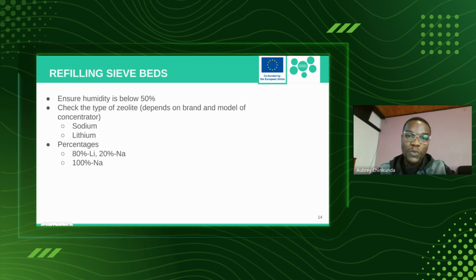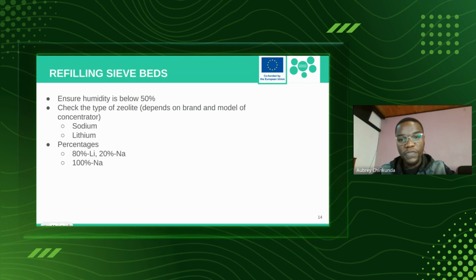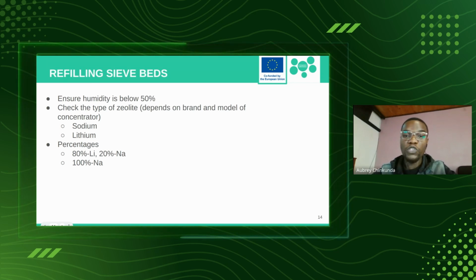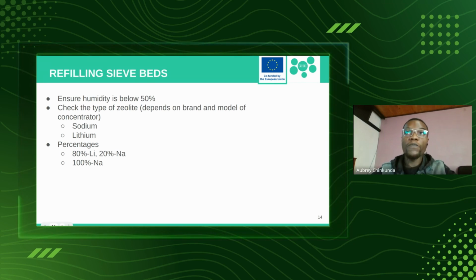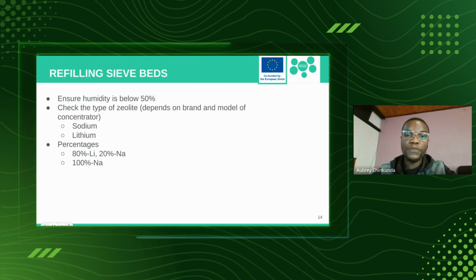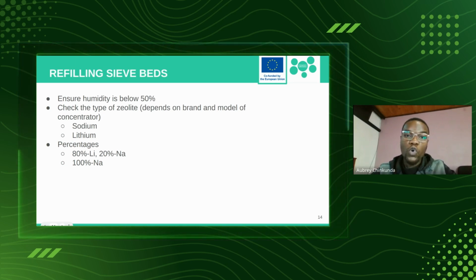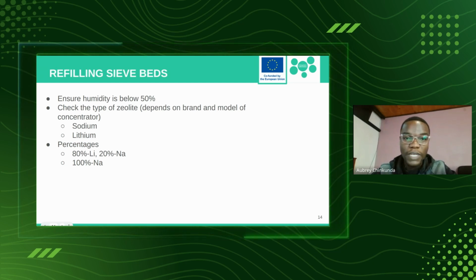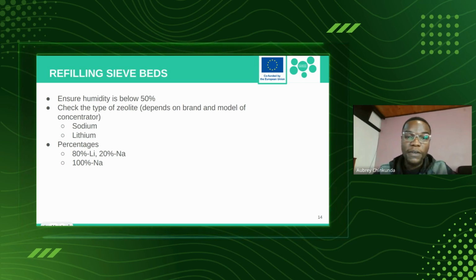After opening the sievebeds, that's when you do the refilling. When refilling, you need to make sure humidity is below 50%, because moisture is the main cause of zeolite damage. You don't want to introduce moisture to the zeolite that you've bought in bulk in 25 kg drums, so you need to ensure the humidity stays below 50%.